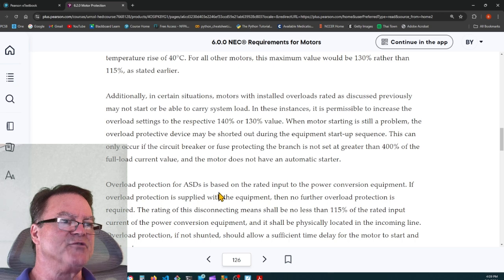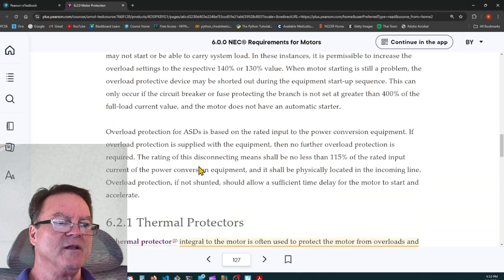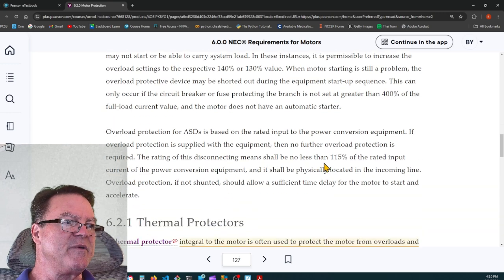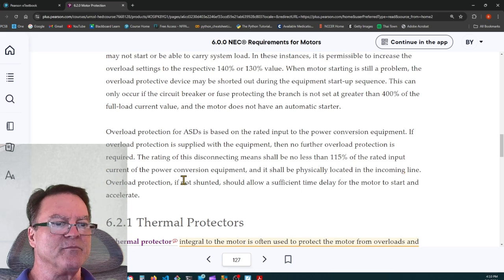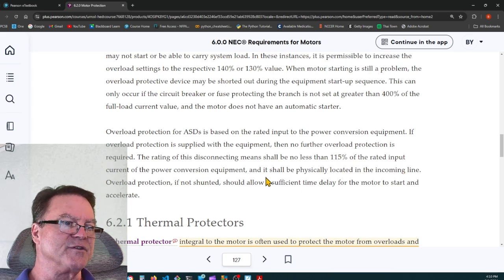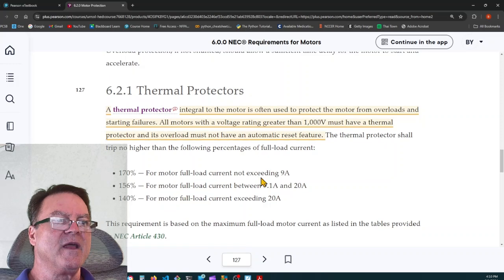So, adjustable speed drives: the protection for adjustable speed drives is based on the rated input to the power conversion equipment. If overload protection is supplied with the equipment, then no further overload protection is required. The rating of this disconnecting means shall be no less than 115% of the rated input current of the power conversion equipment, and it shall be physically located in the incoming line.